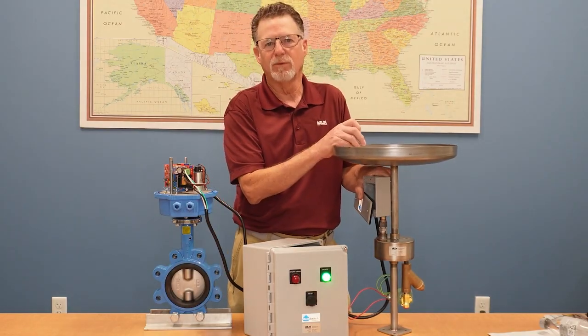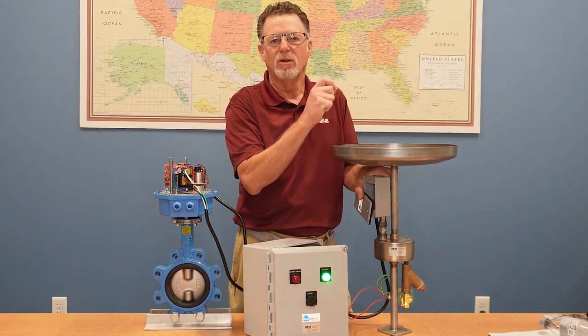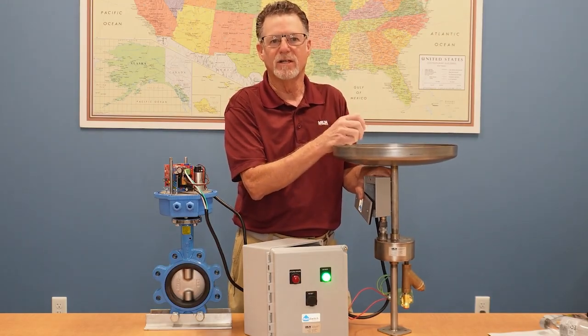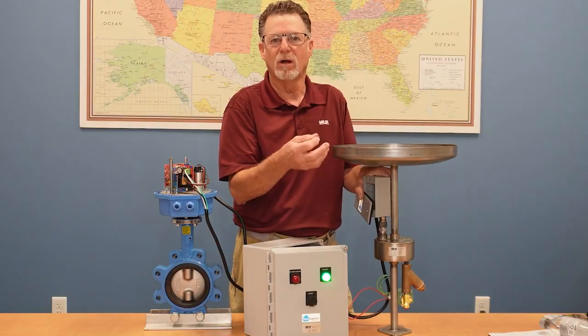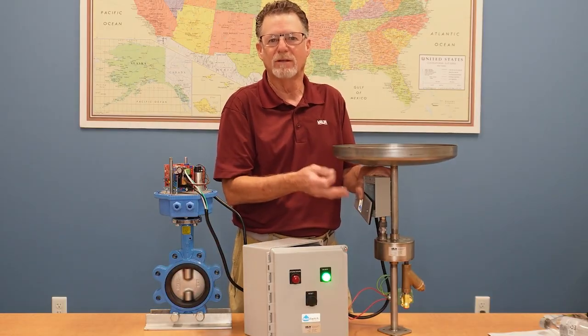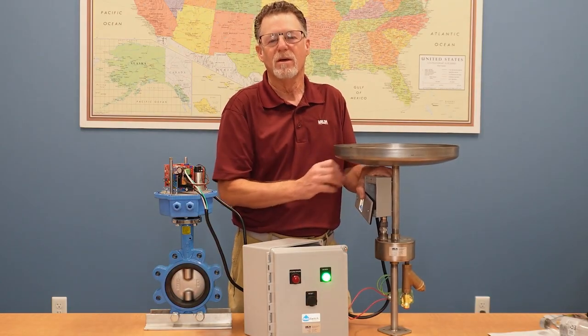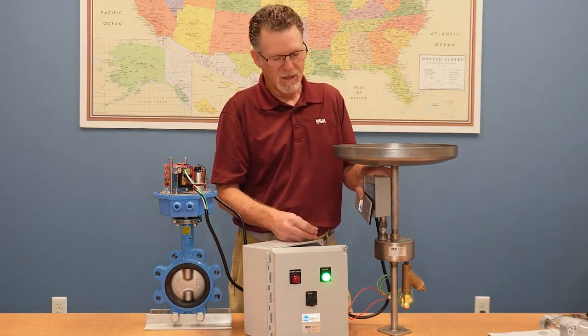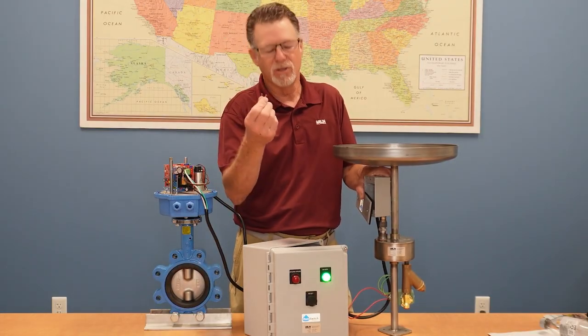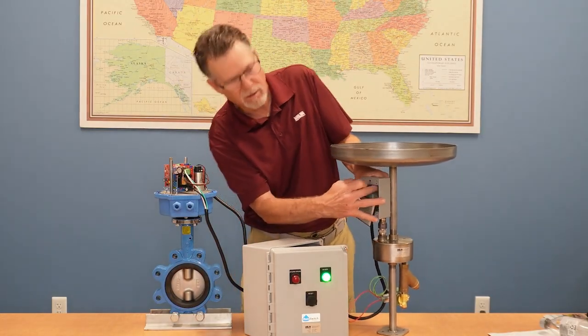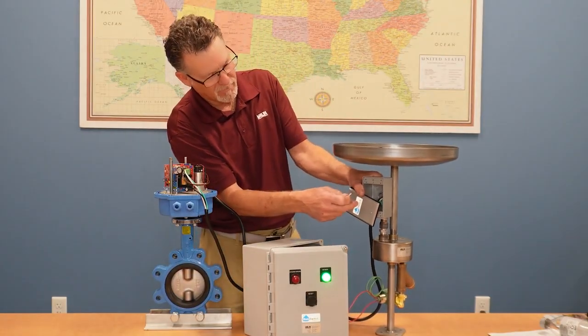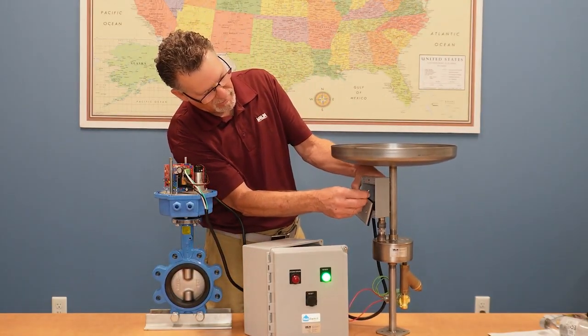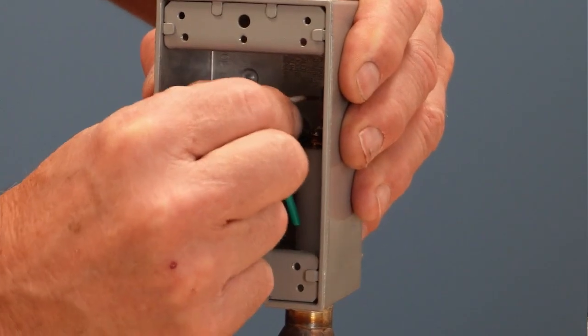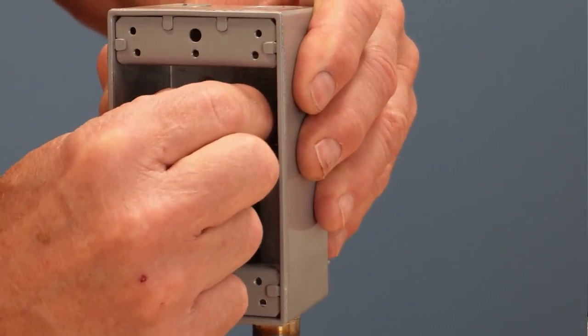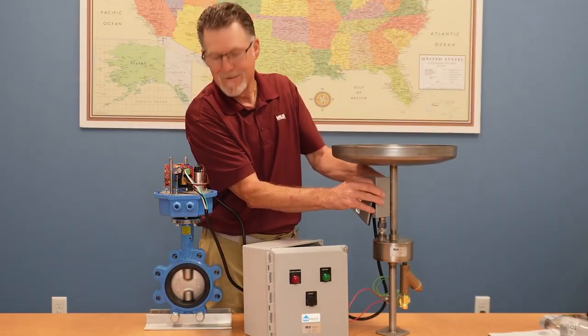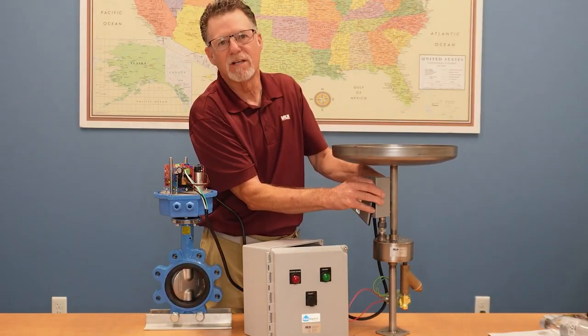One thing for testing: people will install them and test them. You can't use bottled water to test because bottled water is RO water. It's too clean. It won't create the short between the ground and the probe. So make sure you just use tap water. The other way you can do it is just take a little jumper, and there's a ground inside the conduit box, the J box, and the probe. You've got to hold it for 3 seconds because the relay has a 3-second time delay. And now you can see the valve is actuated.